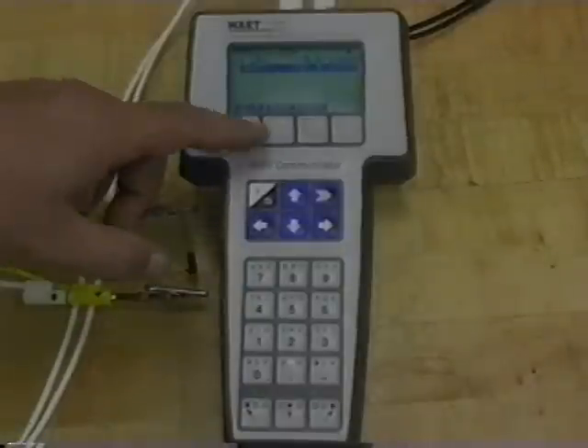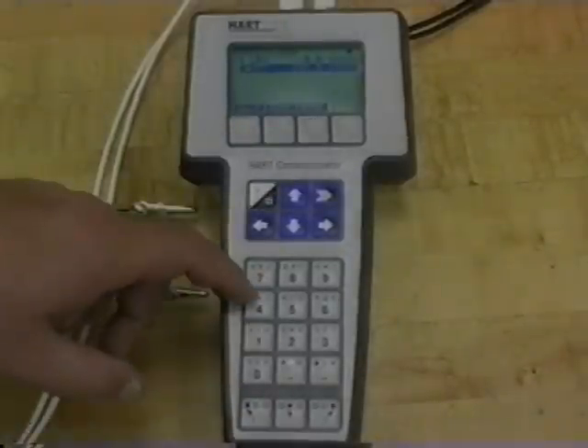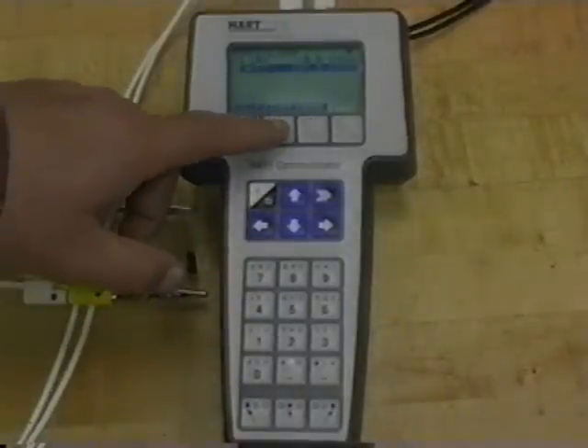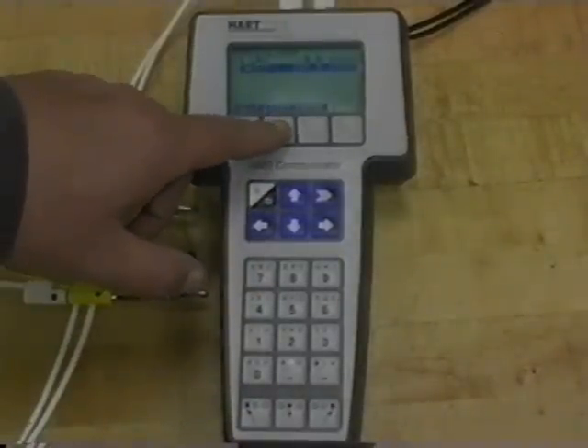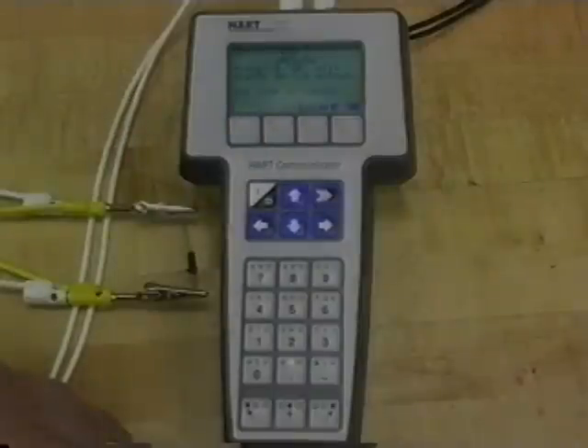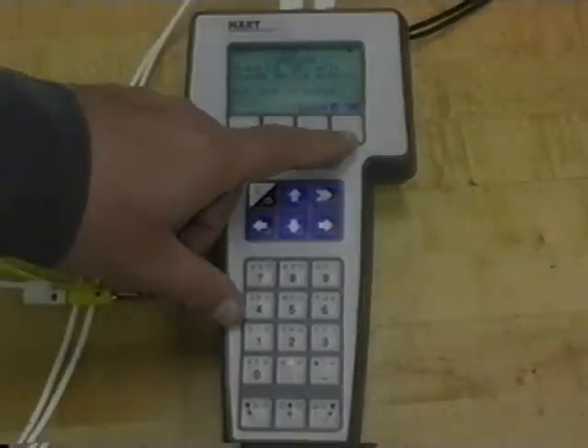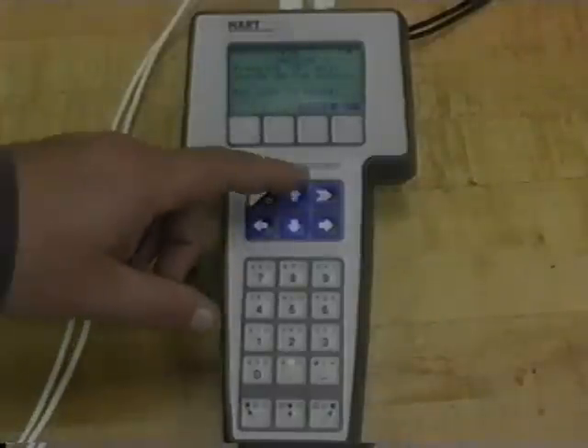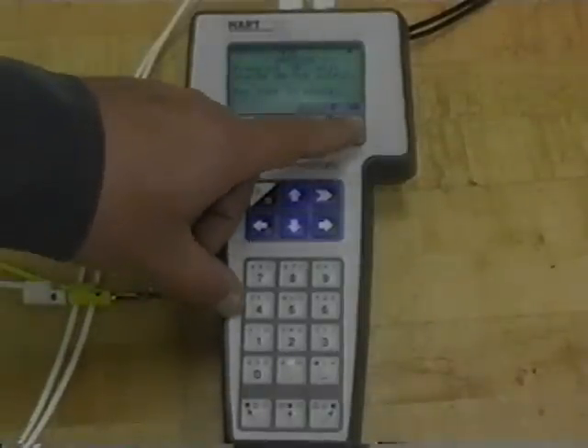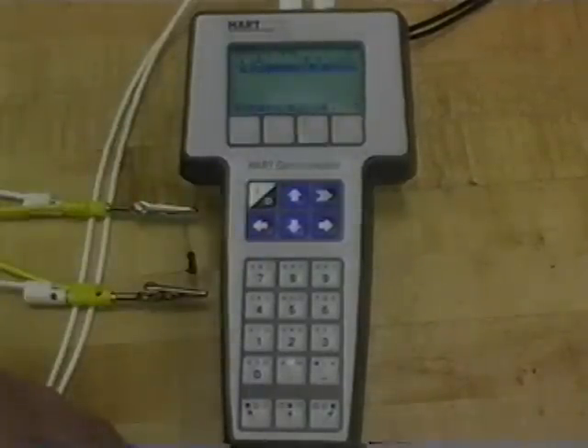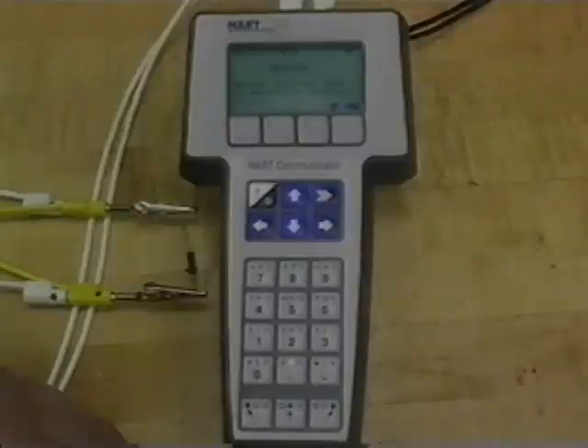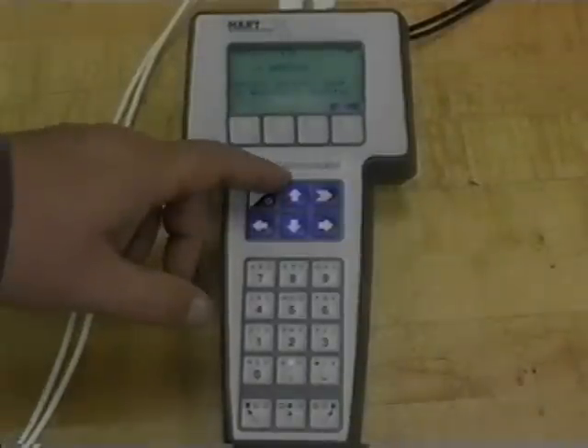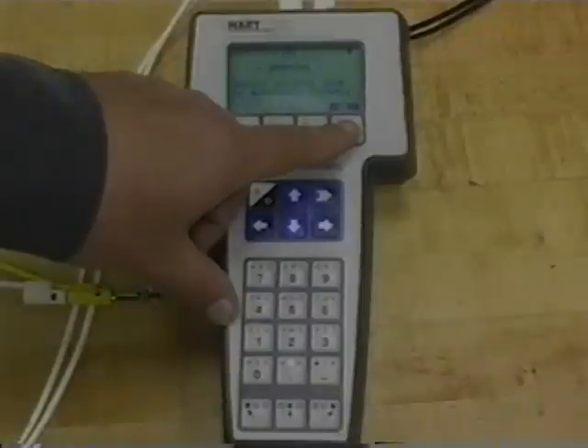The next step is to send the calibration changes that we made with the communicator to the transmitter by hitting the send button. Make sure the loop's in manual. It's not that important right now because we're doing a bench calibration. Hit OK. It's all done. It says you can put the loop back in automatic. Hit OK.